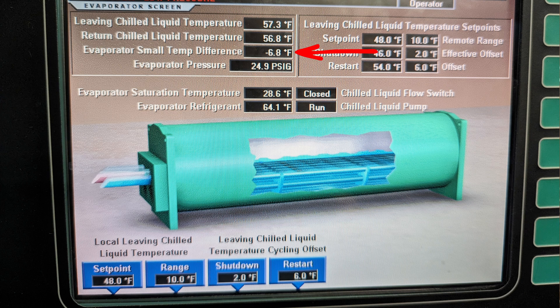The difference between leaving water and evaporator saturation gives you your approach value. The higher the approach value, the less heat transfer is happening — or the less efficiently that transfer is occurring. The lower the value, the more efficient. This approach concept is extremely effective for troubleshooting heat transfer even on a regular split system or RTU — you'd take your leaving air temperature minus your evaporator saturation to get the evaporator approach.